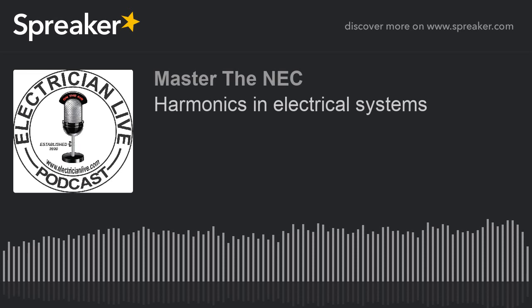Okay. Now, the negative sequence harmonics can cause the same heating problems as the positive harmonics, plus additional problems with various types of motors. And why is this? Because the phase rotation of a negative harmonic is opposite that of the fundamental frequency. In other words, the fundamental frequency goes one direction, and, as we said, the negative harmonic tries to oppose that in the opposite direction. And this will tend to weaken the rotating magnetic field of an induction motor, causing it to produce less torque, thus causing it to overheat prematurely. Okay, so those are the kind of things.